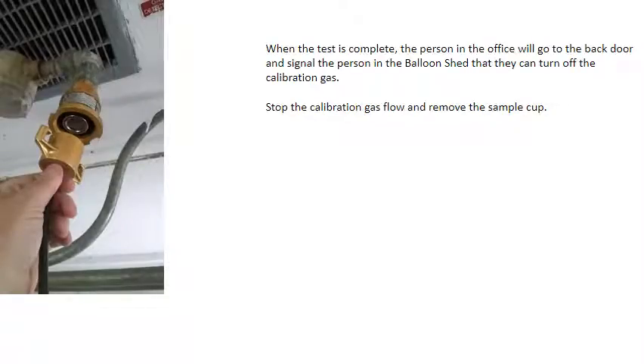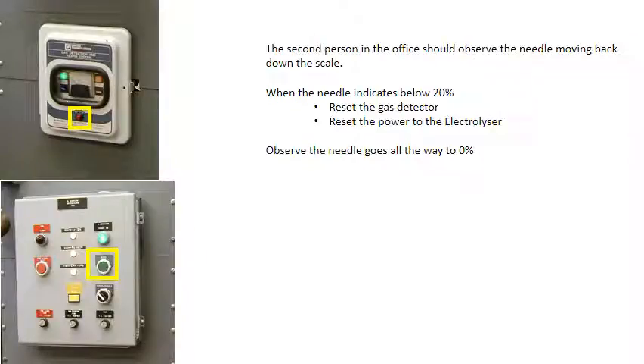When the test is complete, the person in the office goes to the back door and signals the person in the balloon shed that they can turn off the calibration gas. Stop the calibration gas flow and remove the sample cup. The second person in the office should observe the needle moving back down the scale. When the needle indicates below 20%, reset the gas detector and reset the power to the electrolyzer. Observe the needle goes all the way to 0%.